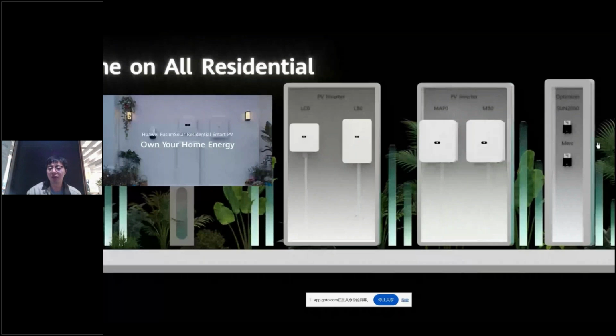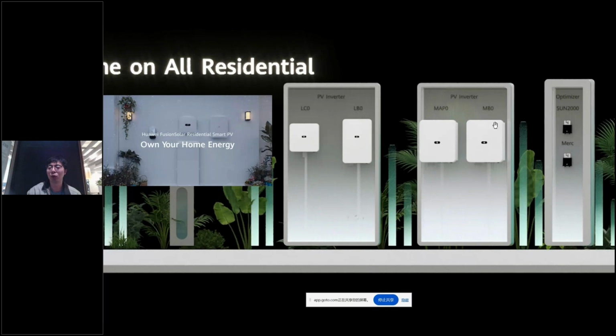For the inverter, we now have 2 single-phase inverters and 2 three-phase inverters. For the three-phase inverter, we have MAP0 and MB0. The power range of the MAP0 is from 5 to 12 kilowatts, and for MB0, the power range is from 12 to 25 kilowatts. Besides that, because space is limited, we still have the M1 inverter, with a power range from 3 to 10 kilowatts.